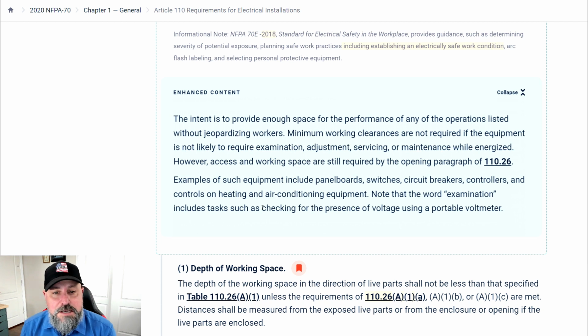Enhanced content. The intent is to provide enough space for the performance of any of the operations listed without jeopardizing workers. Minimum working clearances are not required if the equipment is not likely to require examination, adjustment, servicing, or maintenance while energized. However, access and working space are still required by the opening paragraph of 110.26. Examples of such equipment include panelboards, switches, circuit breakers, controllers, and controls on heating and air conditioning equipment. Note that the word examination includes tasks such as checking for presence of voltage using a portable voltmeter.